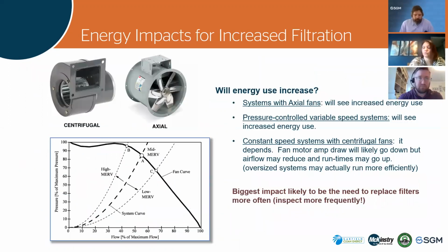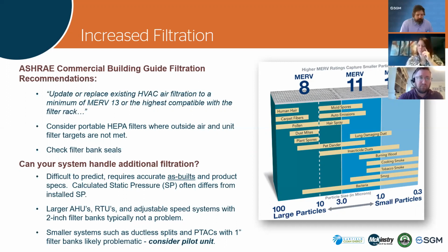One note on the HEPA filters, there are some issues if people are going to try and upgrade to HEPA filters. There's a larger pressure drop, so you really need to increase fan energy use. Condensation can also occur across those filters, which gives mold spores a place to grow. So that's why the HEPA filters that Brian was referring to is more of a standalone unit, to add to an area as a standalone unit. Yep, absolutely. And next discharge slide. To the outside is preferred if they can do that.